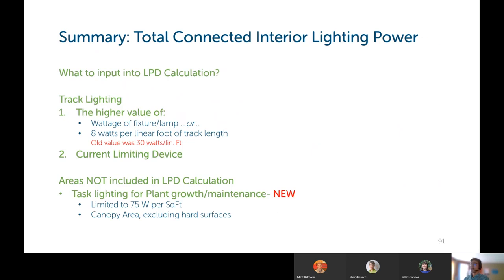So the summary of what you include in your lighting power density calculation, the changes for this code are track lighting. You use the higher value of either the wattage of all the lamps and fixtures that you're tying to your track system, all those combined, or 8 watts per linear foot of track length that will be installed, because it's a flexible lighting pattern. So there's no saying you couldn't put more fixtures in later. The old version of the code stated you needed to use 30 watts per linear foot for track lighting. So 8 watts per linear foot seems to be a lot more closely tied to LED lights that we're going to see installed in track lighting going forward. Or, instead of doing all that, if you have a current limiting device or even a breaker that's tied to the track lighting, you can use the maximum wattage that would be allowed by that current limiting device in your lighting power density calculation.